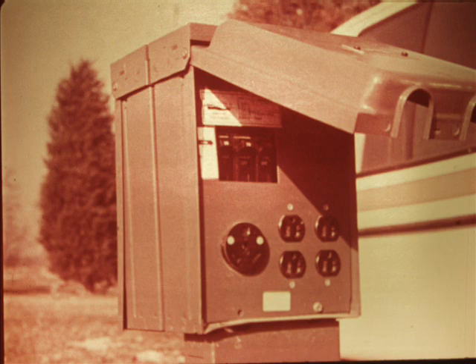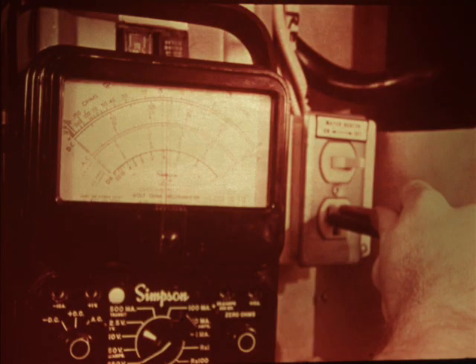First, most campsites don't have the right power supply, and we come in with one 120-volt circuit to feed both master breakers. Then, with air conditioning and a few other appliances turned on, we're calling for more current than the source can supply. So make it a rule to test for a full 120 volts AC available to the power converter.